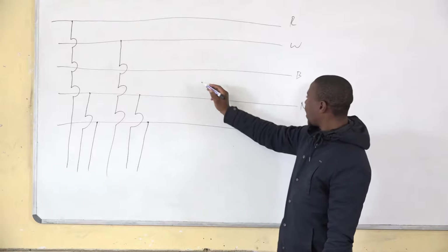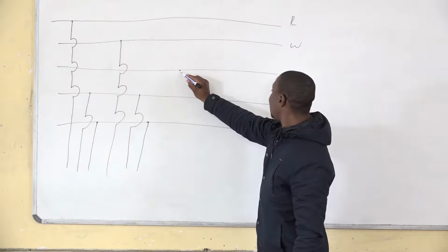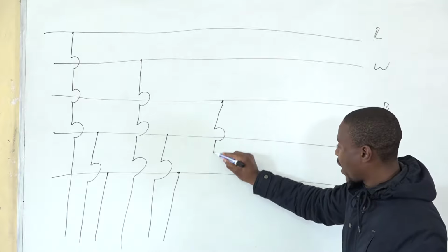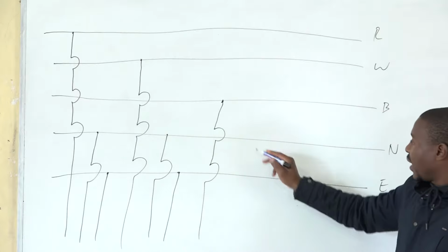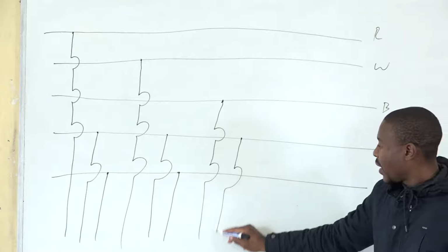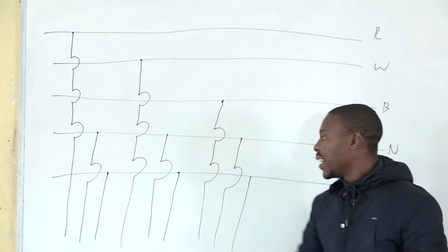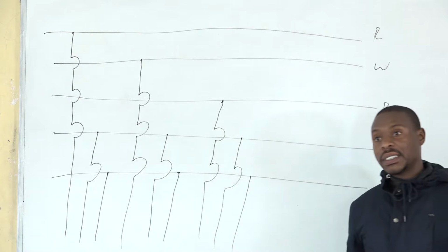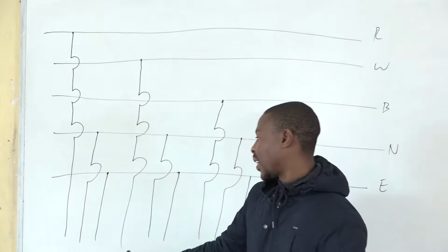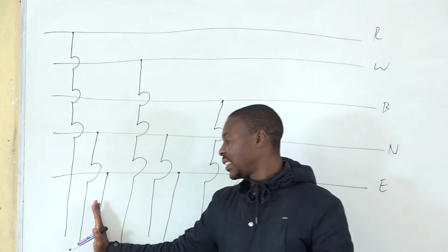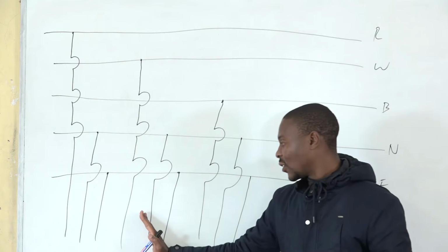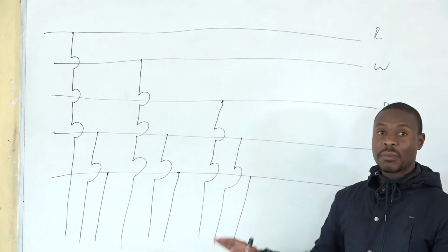On the blue phase, they tap again. This blue phase is a live wire, remember that. Then they take the neutral and earth. Okay, these are only for single phase loads. Then now your load is balanced. For example, this is 10 houses from your street, 10 houses from my street, and 10 houses from the other street.